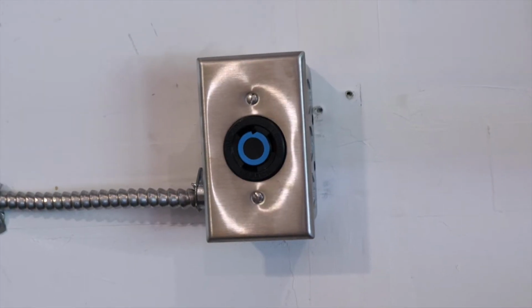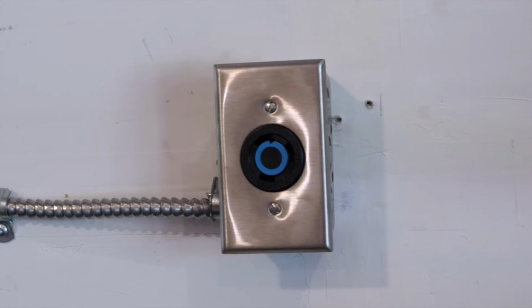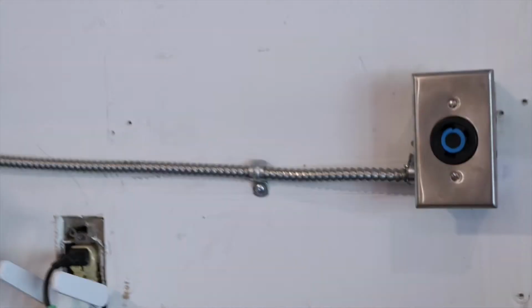So what I had the electrician do was install this L6-30R outlet, which is 30 amp 240 volt, on armored cable along the wall up here, down here, into the basement, into the panel downstairs, which is on a 30 amp circuit.